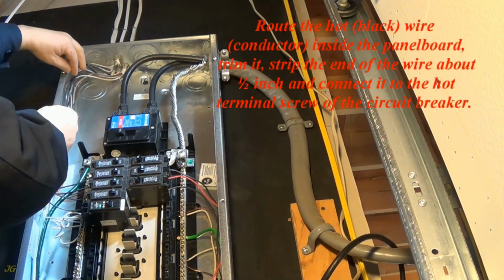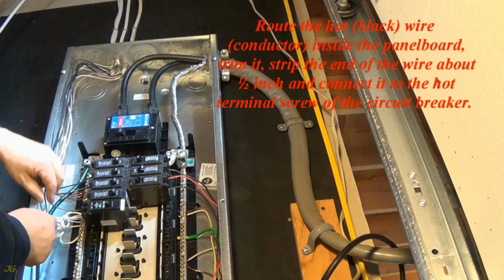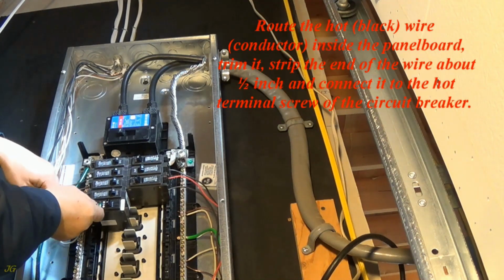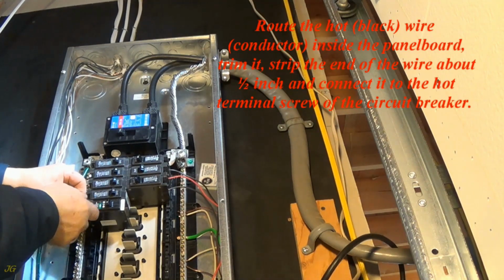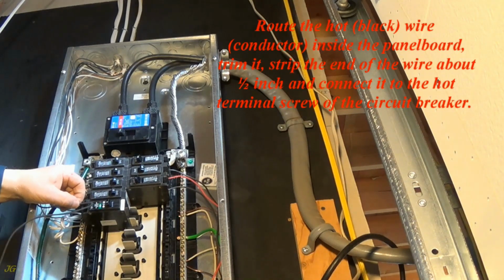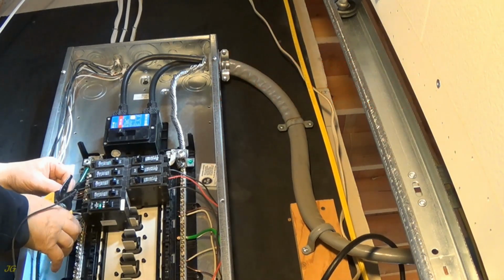Route the hot, black, wire, conductor, inside the panel board. Trim it, strip the end of the wire about 1/2 inch and connect it to the hot terminal screw of the circuit breaker.